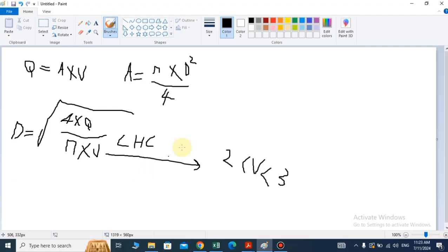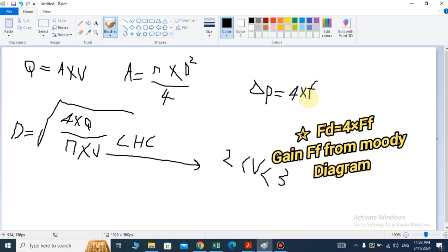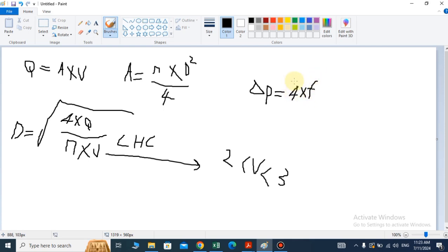We need to understand the concept of differential pressure or frictional factor, which means understanding the formula. We need the Fanning factor, which is actually the Moody factor that we get from the Moody diagram, multiplied by 4 to turn it into the Darcy factor. Again multiply this number by the density of the liquid and the velocity powered by 2, divide this by 2, and multiply all this by the length or equivalent length of the pipe, and divide this number by the internal diameter of the pipe.